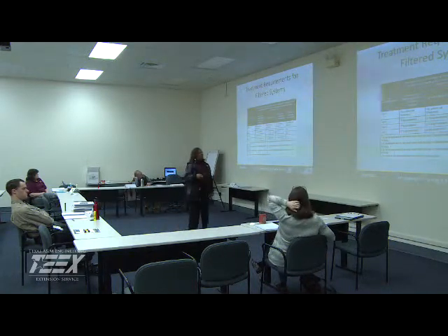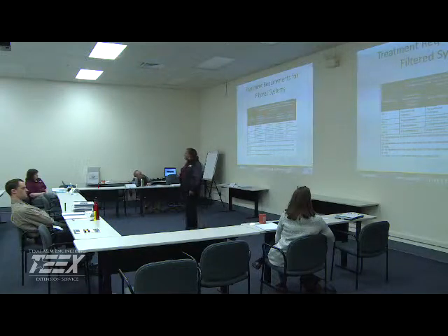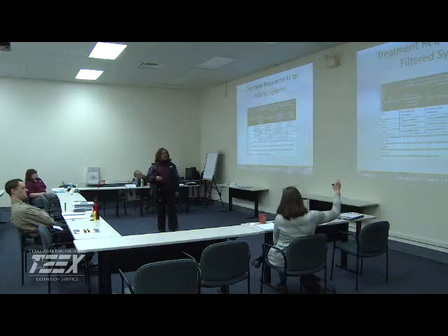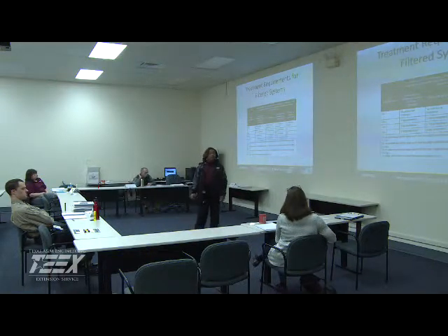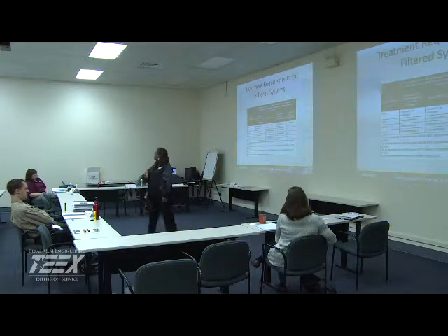For your sand filters or diatomaceous earth, 2.5-log. And this is where the state has some say in how you're going to remove it. They gave that leeway back to the state. And that would be the membranes, 5.5-log. Right, your various types of membranes: nanofiltration, reverse osmosis, ultrafiltration.